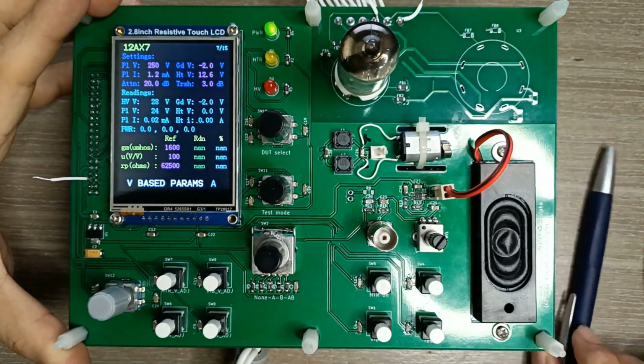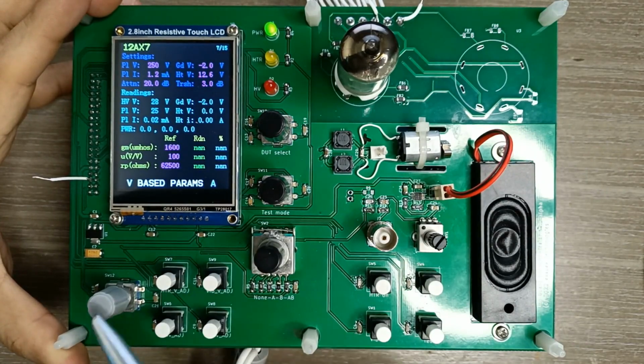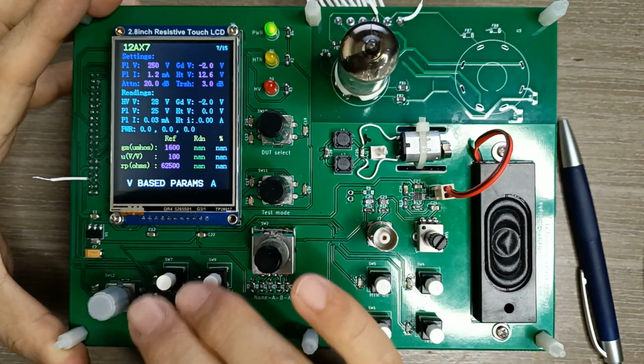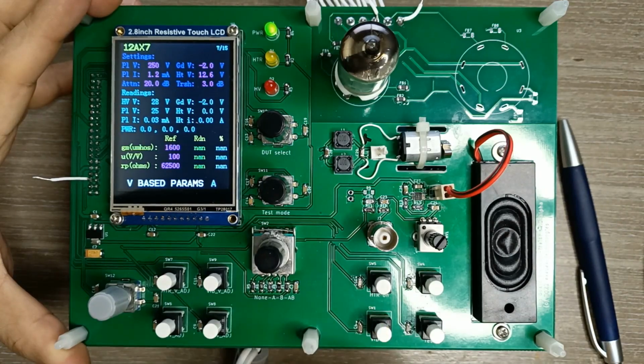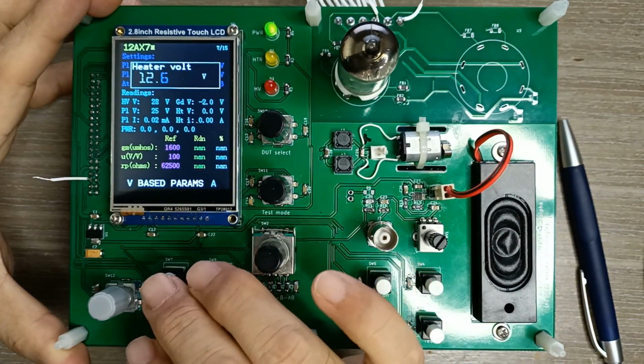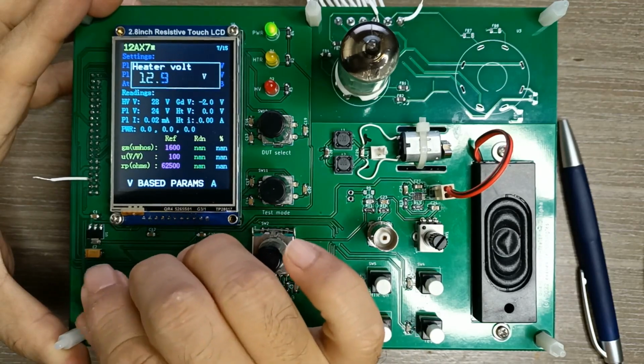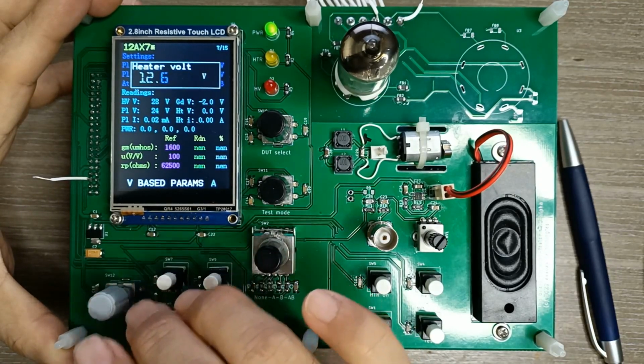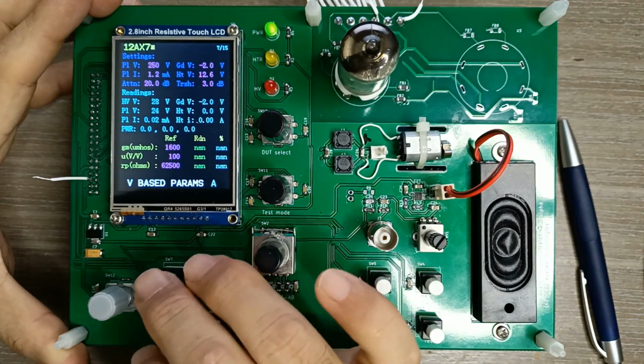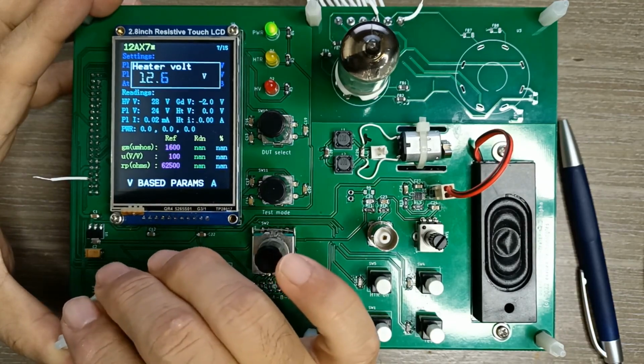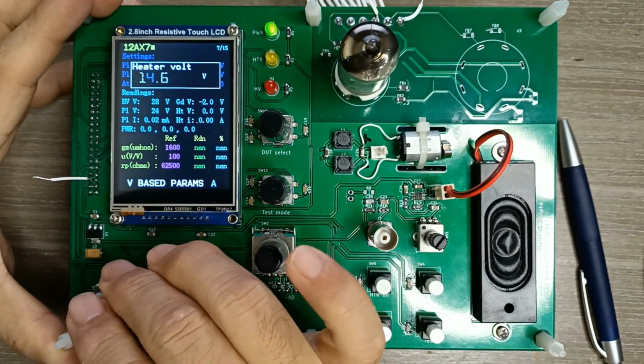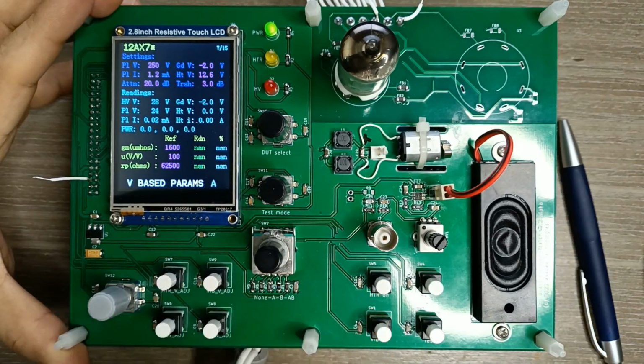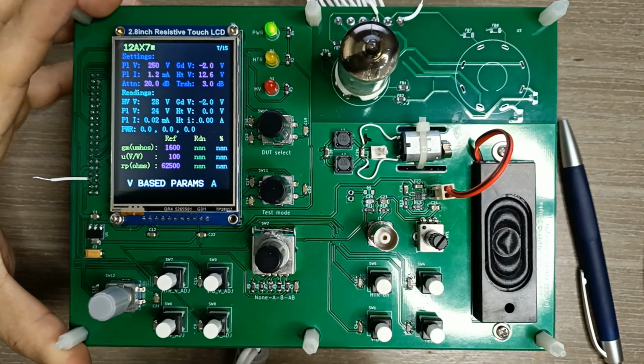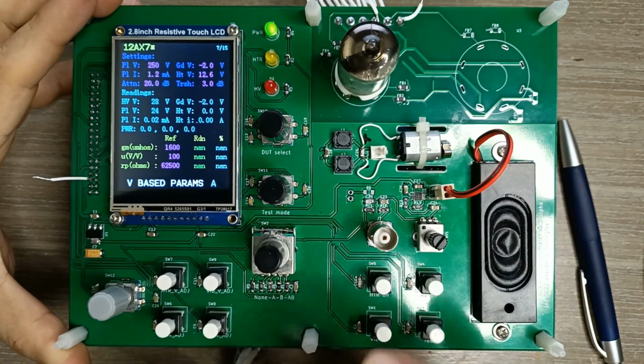Okay. And here we have 4 push buttons and the rotary knob, and this allows us to do a voltage adjustment or current adjustment on the fly. So this one is a heater voltage adjustment. Here it allows us to adjust the voltage of the heater's power supply, and the increment by default is 0.1 volt. If you push this button, you can select the increment of 1 volt. It varies setting by setting, so if you want to adjust different values, the increment can be selected accordingly.